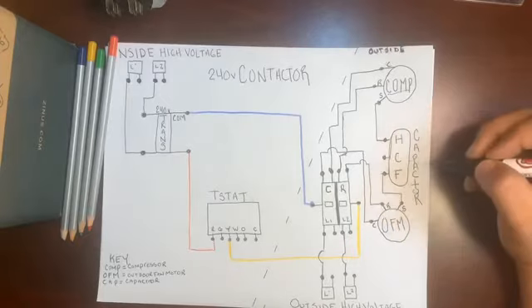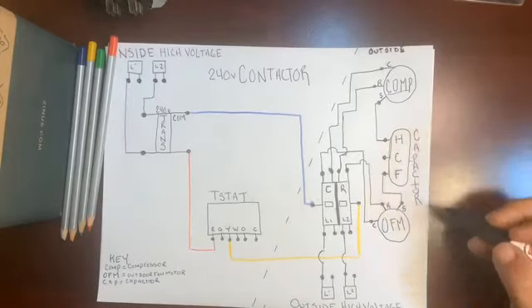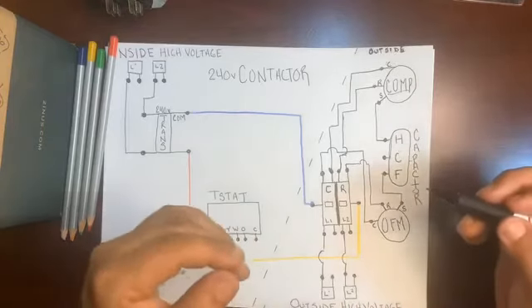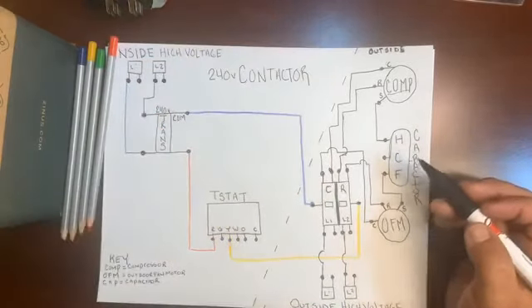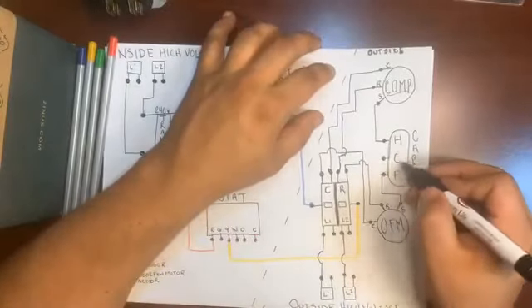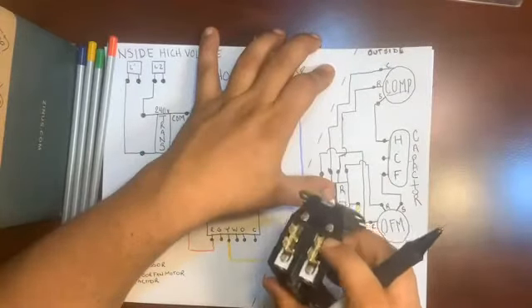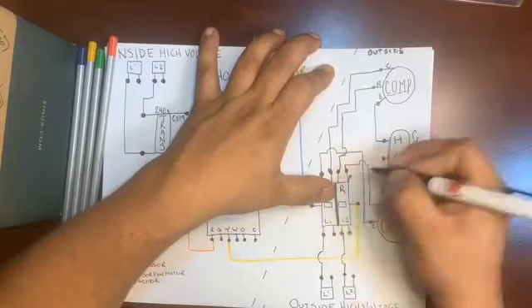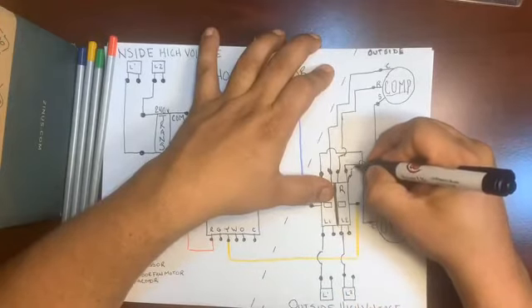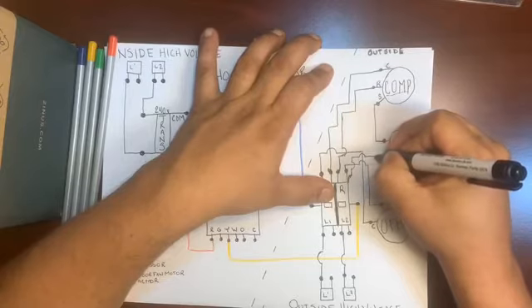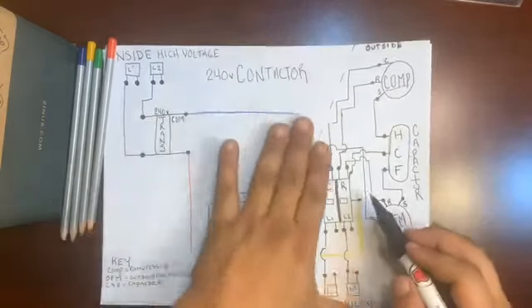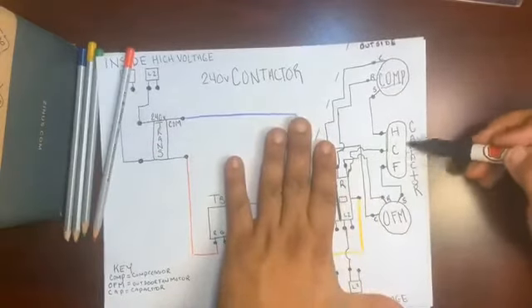So what does that leave? That leaves common on the capacitor. You naturally want to put it with the other commons, and absolutely, that's what we've learned the whole time. Only in this case, every capacitor is fed on the run side. And that's why we have 4 legs, because one of these third legs will come off here, come off the back, and head up, jump over, head over, another bridge, and the run side is what feeds the common on the capacitor.